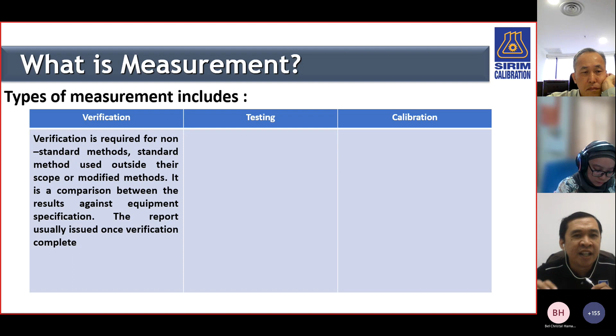Okay, for this example, let's say you have a machine that needs to run at 30 degrees Celsius. Then you have 1 unit of infrared thermometer to check whether your equipment is running at exactly 30 degrees. You check, and the display on the infrared thermometer is 30 degrees and the equipment is 30 degrees. Then it means this machine passes, as it operates as per its specs of 30 degrees Celsius. Then the report will be issued. That is a verification. In your report, it usually states pass or fail.